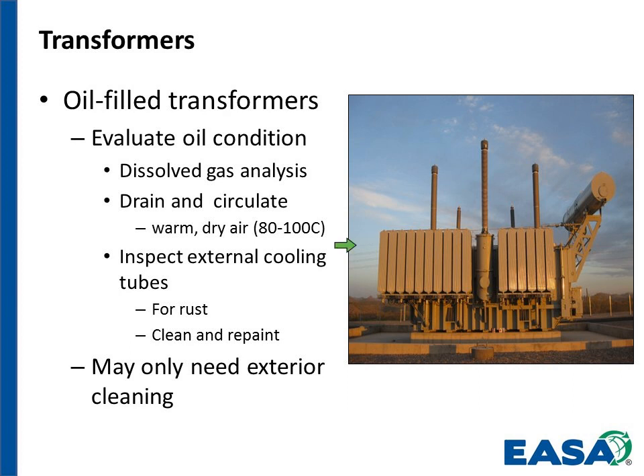It's probably only the exterior of the transformer that's been immersed, that has water in it. We can do dissolved gas analysis to check for water for transformers, and there's nothing here in this slide, but for transformer oil, the recommendation is not over approximately 35 to 38 parts per million of water. So that can be analyzed and checked to determine if we need to do something. External cooling tubes, the outside of the transformer needs to be cleaned to make sure that we've flushed off any salt residues that might cause rust down the line. Any rusting that's present, we want to clean, sand, and repaint.